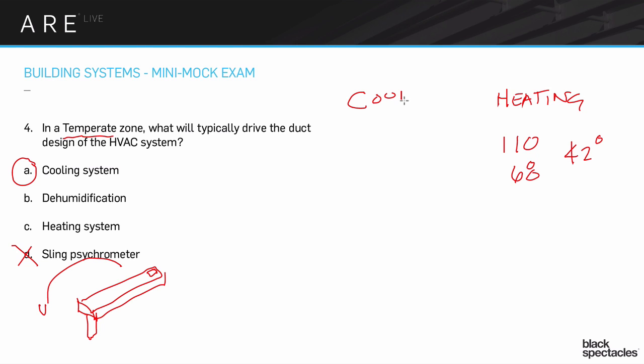In the cooling, let's say our room temperature is, I don't know, 75. Well, the air temperature that's going to be blowing through is probably going to be about 55. Now it could be lower, it could be a little higher, depends on a couple different things. But very quickly you realize, wow, that's only a 20 degree difference.